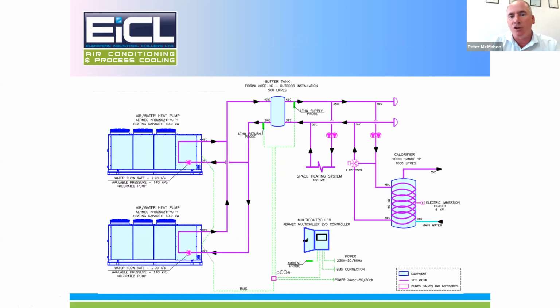I have a graphic here just to show you how it's installed. So you can see here the multi-chiller controller is monitoring your load by monitoring the temperature difference. There's a direct correlation between the delta T difference in return temperature and supply temperature with load. Obviously, it's proportional.